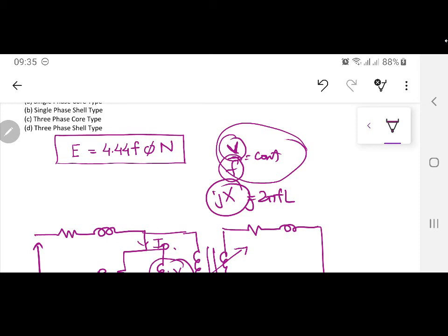The distance from that winding to the core, which is electrically at neutral or grounded, is not going to require much. In this low voltage winding of this transformer there are many taps, maybe it is 12 volts. So 12 volt does not require that much insulation. But when that 12 volt turns are done, certainly there are going to be fewer turns. Afterwards, a paper insulation again is done, and on that insulation you are going to do the high voltage winding. Everything remains very simple if the voltage is near about 400 or 500 volts.